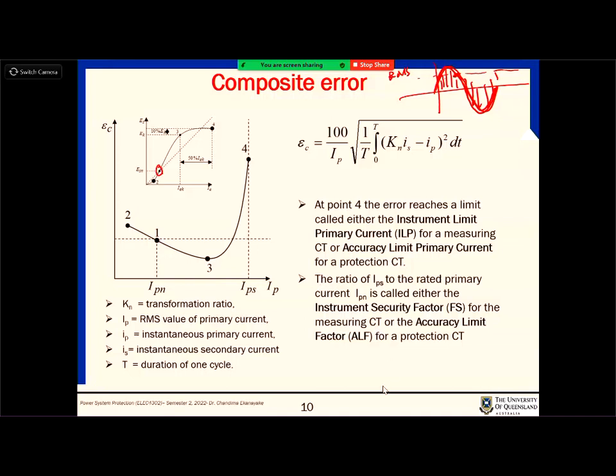Ratio is called instrument security factor for measuring CTs and accuracy limit factor for protection CTs. So when you are looking at a CT data, when the supplier is providing it, they have to provide that. When you look at the table, you will see the accuracy limit current, primary current, or accuracy limit factor, ALF. Those are given with the product, so that you can do the designs based on that. Okay.